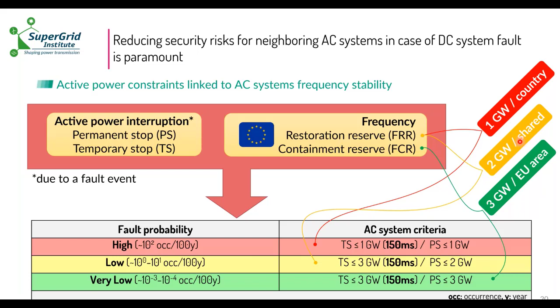And these probabilities are used to classify, let's say, some events and give some guidelines to the protection design. So as a matter of example here, where there is a line fault in the HVDC grid, the one here in red, you cannot allow any of the converters to block. You need to be selective and isolate this line.